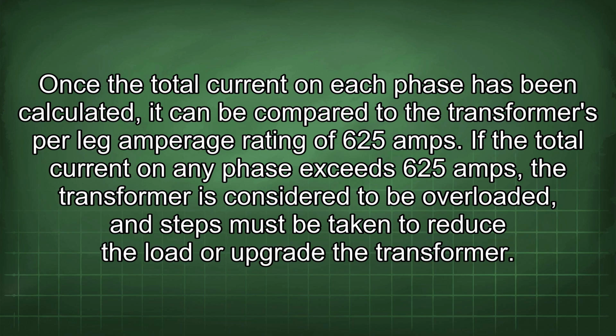Once the total current on each phase has been calculated, it can be compared to the transformer's per leg amperage rating of 625 amps. If the total current on any phase exceeds 625 amps, the transformer is considered to be overloaded, and steps must be taken to reduce the load or upgrade the transformer.